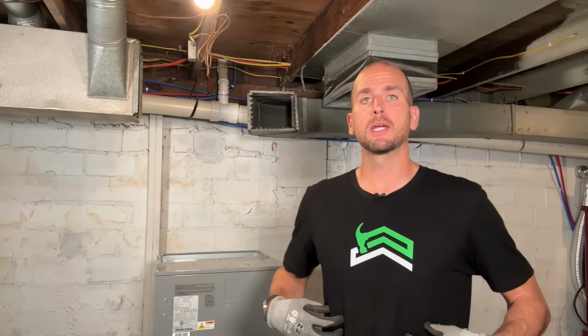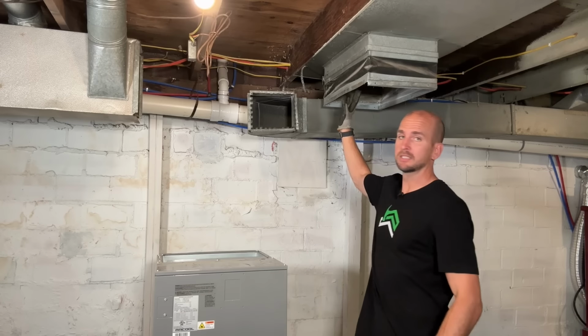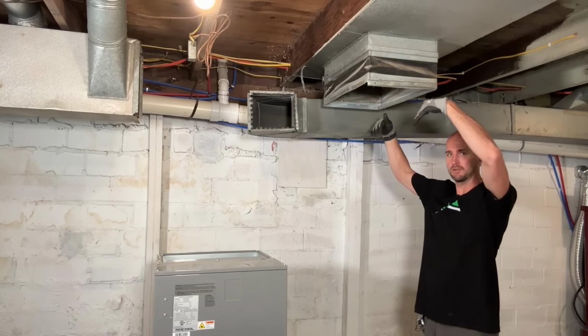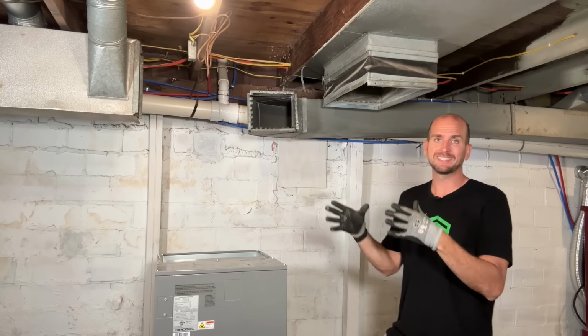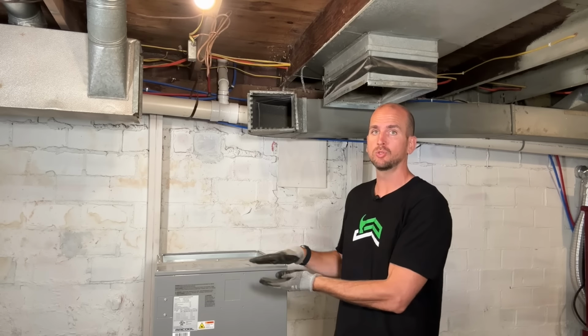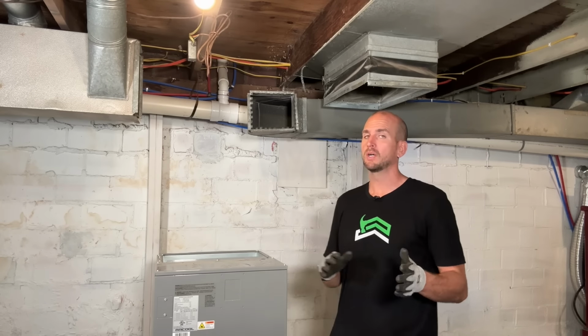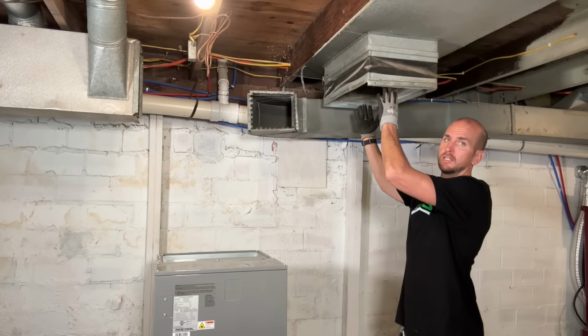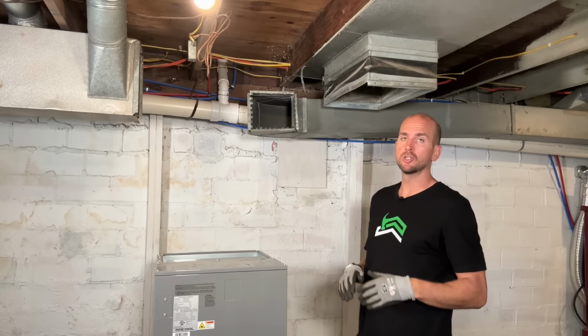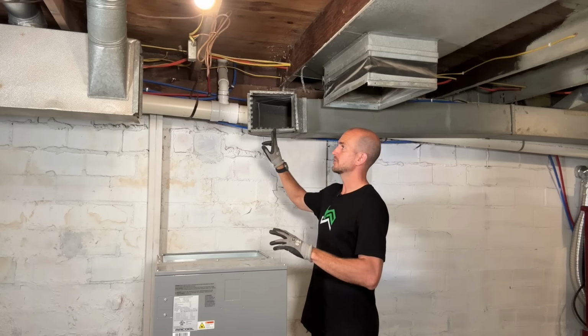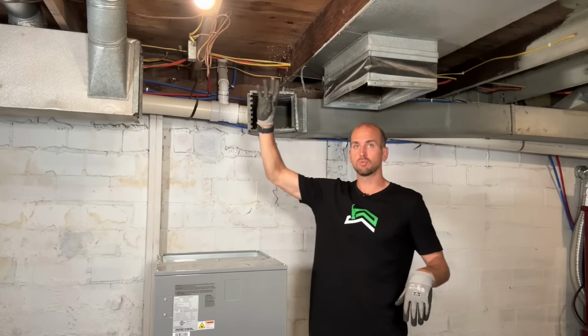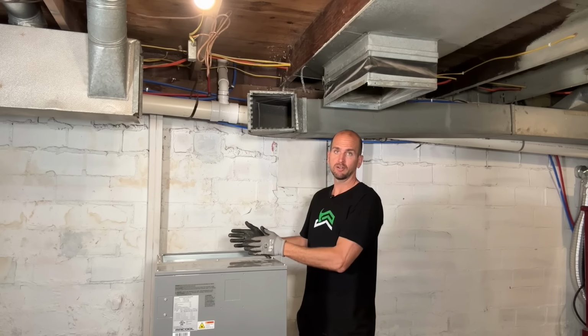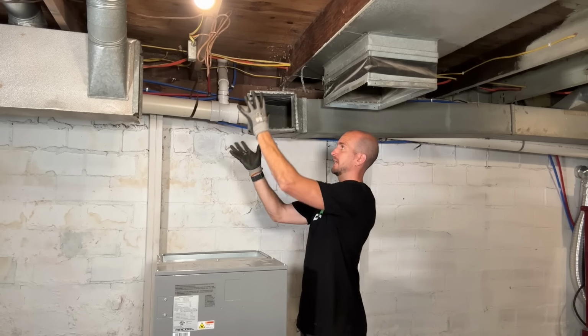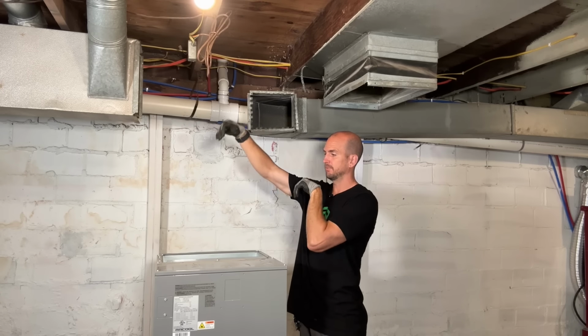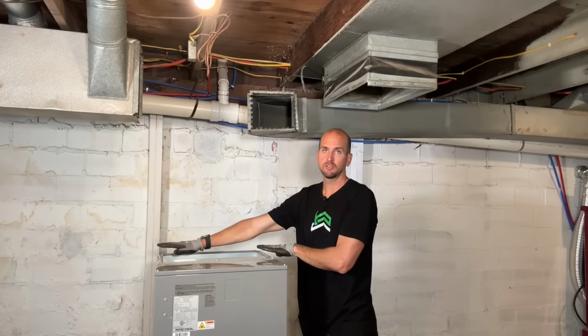So first up, I am going to tackle getting all the ductwork together, getting everything lined up, everything from my existing cold air return. So this is going to come down and that's going to go into the bottom of a stand and plenum that the actual Mr. Cool unit is going to sit upon. So we will have some fabrication to get the existing ductwork to line up with what we're bringing in new. And then we'll have to do quite a bit of work again, bringing my 2 ducts that will go out to all my vents or registers in the house down to the actual air handler here. So I'll probably tie these together in kind of one plenum and then build some custom fabricated sheet metal down to actually fit up to the Mr. Cool.